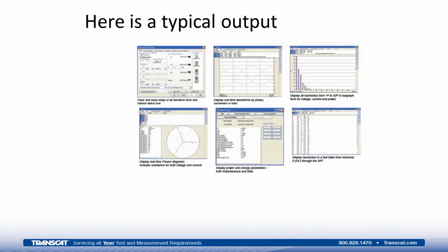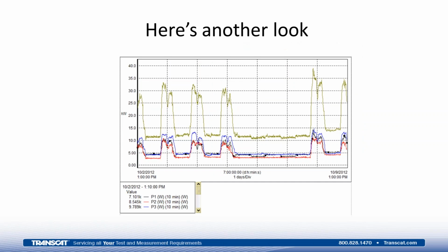Typical outputs could be anything from a screen capture of a waveform to harmonic information to graphs of energy over time. A very typical graph might look something like this. This would be a watt-hour graph that was being accumulated. You could see kilowatts on the left-hand side, and you could see the timestamp of 1 division per day across the bottom. And the 3 lower graphs, the red and the blue, and there's a black in there, it's a little hard for you to see, represent the individual phase loading, and the gold represents the total energy accumulation.